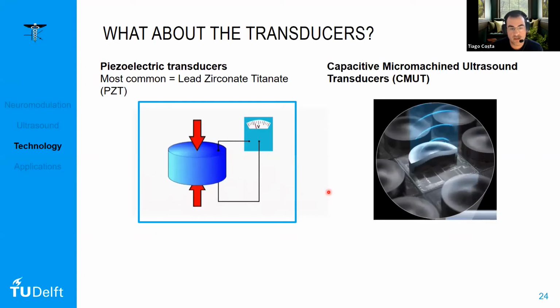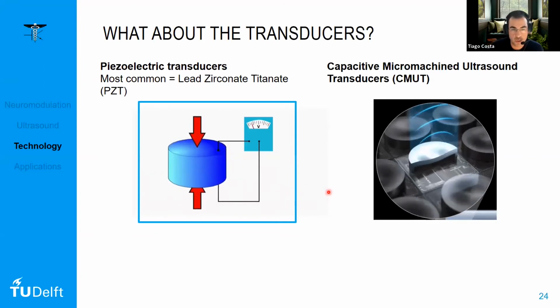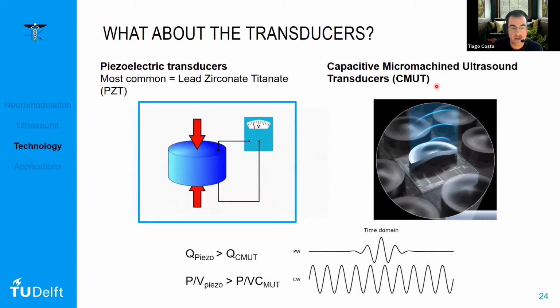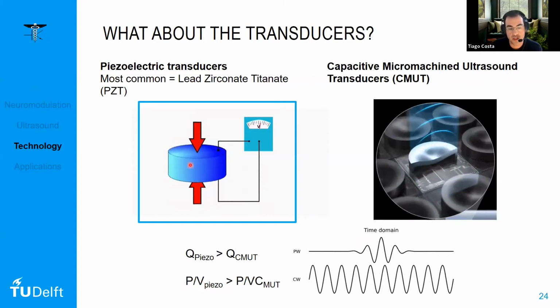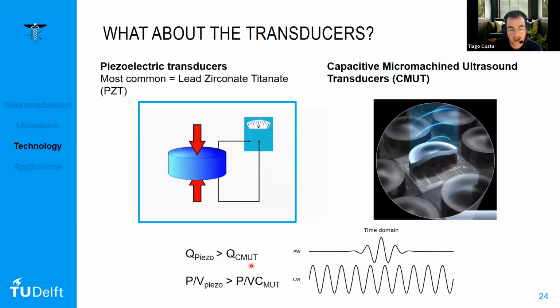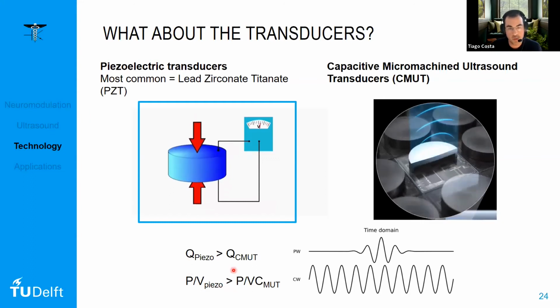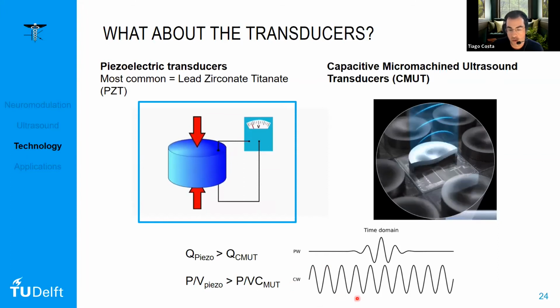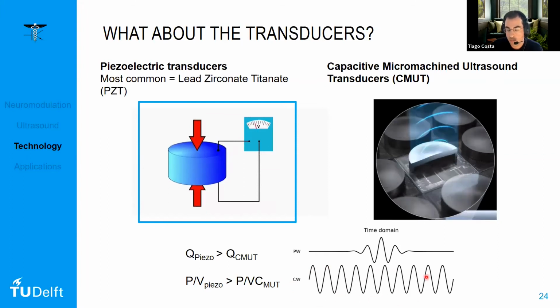Well, for these applications, we use piezoelectric transducers, even though CMUTs are now also being widely explored for neuromodulation, but the fundamental properties of these two are different. The quality factor of the piezos is normally higher than CMUTs, and the output pressure per volt applied is also larger. A larger quality factor means that the energy will be more concentrated at the resonance frequency, which is good to maximize the focal pressure. And this is the type of signals we use for neuromodulation. They are bursts of continuous waves. So that's why piezoelectric transducers are more suited for this.